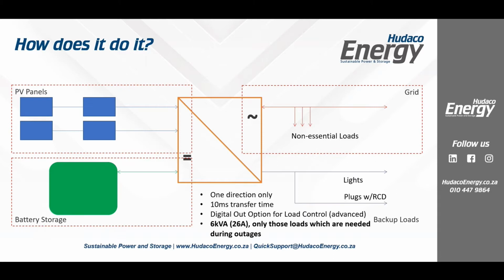And then finally, the backup loads. Now the backup loads, you can see we've got drawn here, we've got lights and we've got plugs. It could be plugs, could be any other equipment which requires earth current leakage. So your residual current device or your earth leakage device. Please make sure that if you have any plugs running on here, you have to have an RCD in place. Normally we separate the lights out so that if there is an earth fault somewhere, and especially at night, the client's still got lights and they can see everything that they need to see.